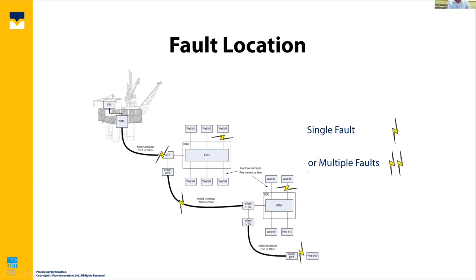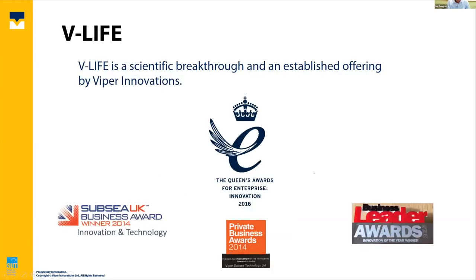So as a subsea operator, you have a challenge. Monitoring IR is not the only thing you need to do. This was a challenge which we, as a company, faced. We had a number of clients in the North Sea, and we saw that one of their biggest problems was insulation resistance and electrical failures. But the only solution when IR got to a low level, or when the system failed, was to go out, locate the problem, and replace the hardware. If the hardware was an umbilical, and your umbilical has failed, the client then got into some commercial decisions, because if you're close to end of field life, it may not be economically viable to replace the umbilical. So a simple insulation resistance failure led to early abandonment of the field. The commercial consequences were quite high.